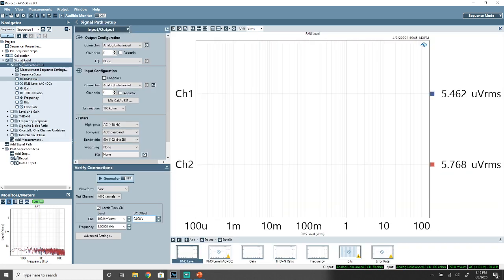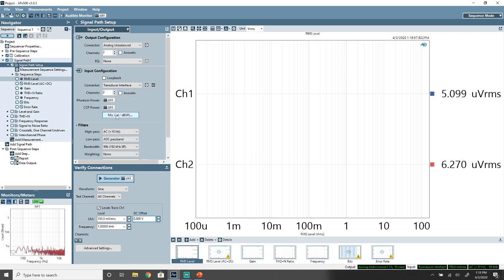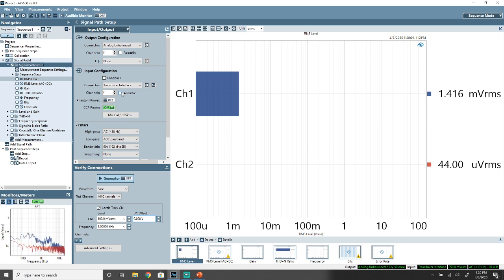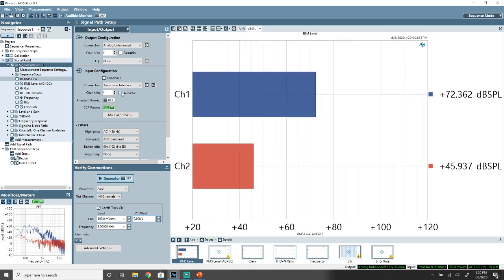And of course, I'm going to start the way I always do, by setting up my inputs and outputs. And I'm more or less going to do the exact same thing that I just showed you. On the input side, I'm going to choose the transducer interface. I'm going to turn on the CCP power. I'm going to check the acoustic box so that my units get measured in dBSPL. I'm going to go to my mic cal, and I'm going to calibrate channel 1 from TEDS again.